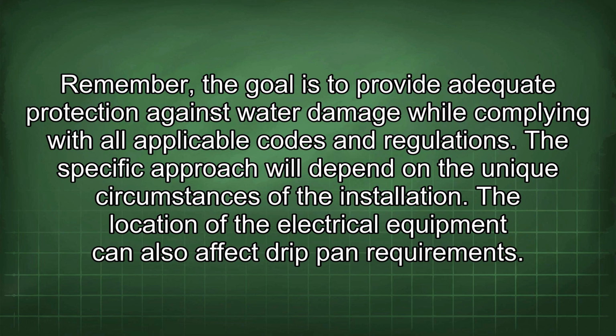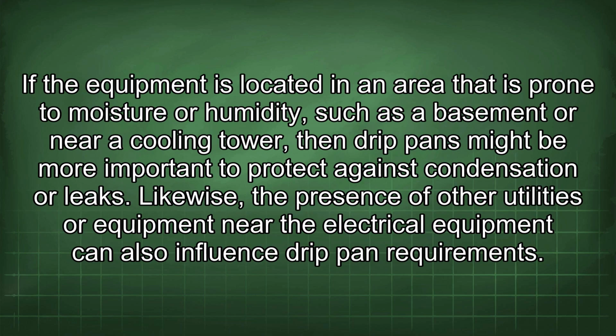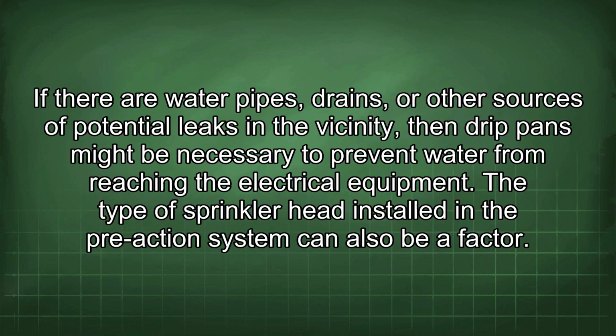The location of the electrical equipment can also affect drip pan requirements. If the equipment is located in an area that is prone to moisture or humidity, such as a basement or near a cooling tower, then drip pans might be more important to protect against condensation or leaks. Likewise, the presence of other utilities or equipment near the electrical equipment can also influence drip pan requirements. If there are water pipes, drains, or other sources of potential leaks in the vicinity, then drip pans might be necessary to prevent water from reaching the electrical equipment.